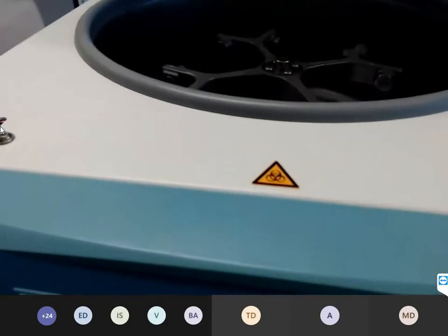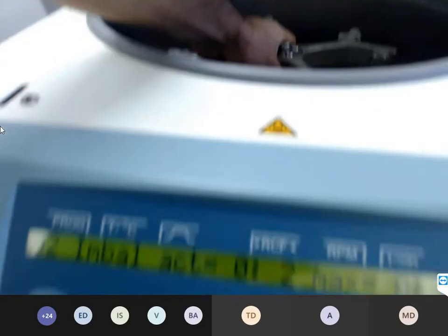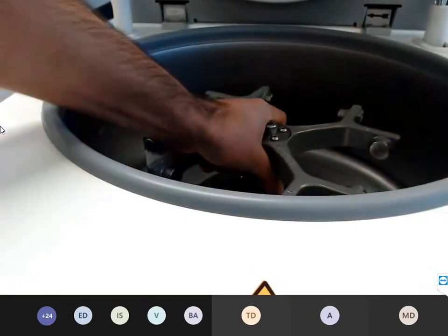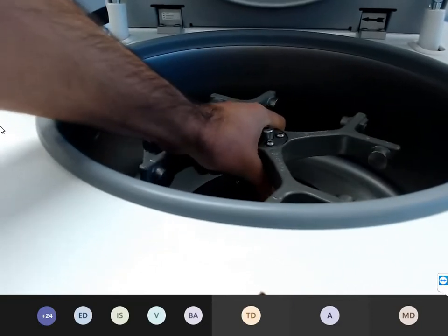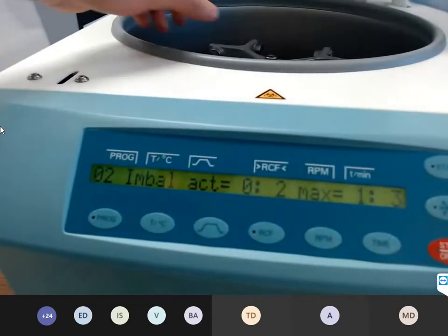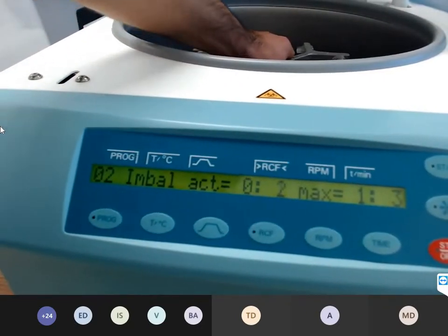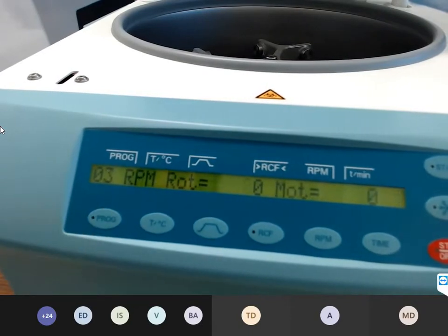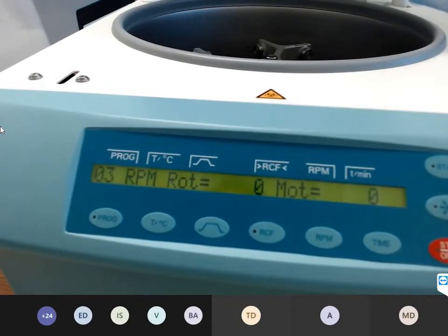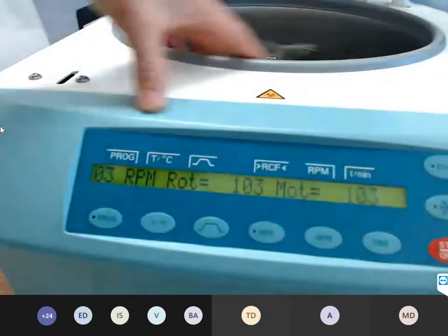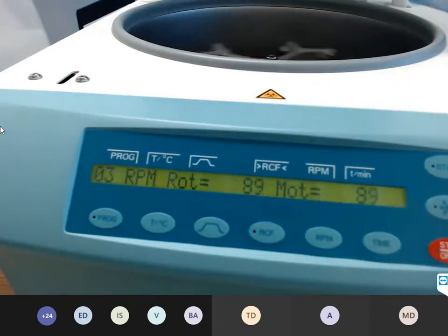If you want to change this act, do this here. We simulate imbalance, and then you can see the values change. That means it works. We have two sensors here. One sensor is on the top of the rotor and one on the bottom of the motor. Turn the rotor and it's the same. These two sensors work, it's fine.